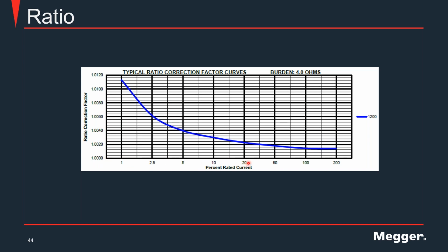Remember, I'm not going to have zero error, but I can use these curves to know, depending on how much current is circulating, what is the correction I have to do to my measurement in order to make a measurement as accurate as possible.